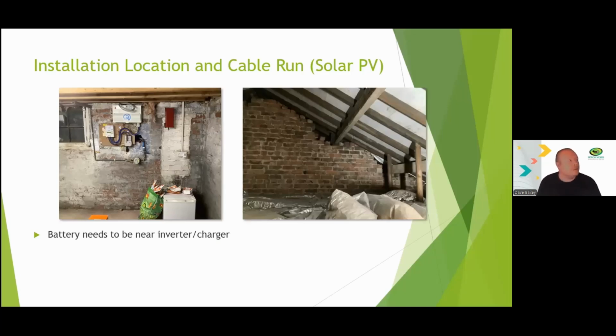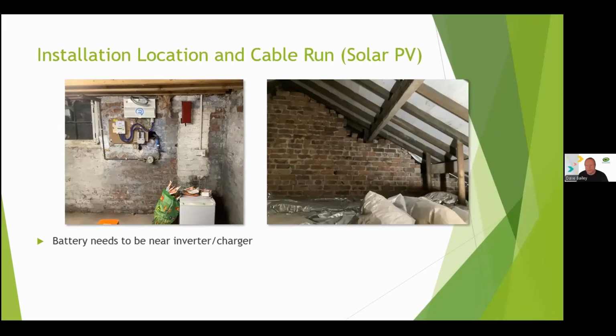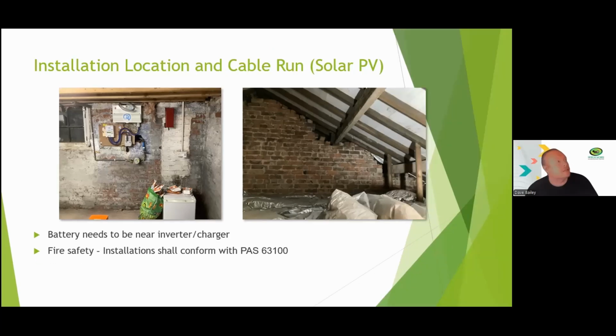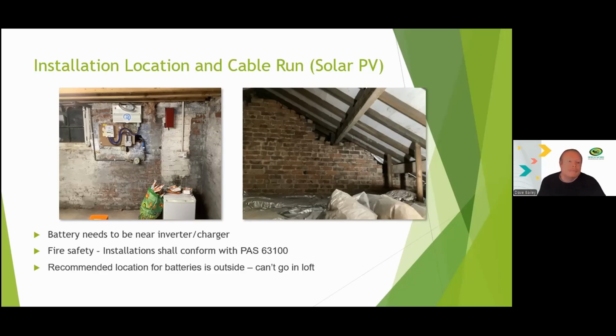In the past, a lot of solar installs were done in lofts. While this isn't particularly a problem for an inverter, batteries can no longer be installed in lofts. While we await the next amendment to the 18th edition, coming in 2026, there's a PAS document, 63-100, for fire safety, with recommendations on where you can install a battery. The recommendation is outside.